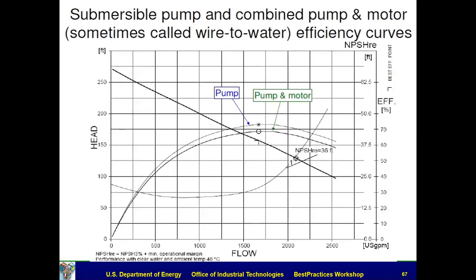Here's just some curves on a submersible pump and combined pump motor efficiency curves. So these are efficiency curves. You can read efficiency over here. And it just shows, like this might be a selection point. This would be the pump by itself, but when you consider the motor inefficiency, that would be the combined efficiency. Net positive suction head required is over here and read on this scale, 36 feet. And I guess this is the actual pump curve over here, or flow versus head. Interesting.